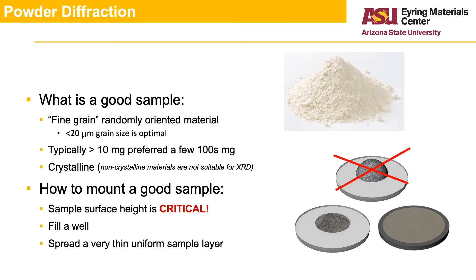First, we make a good sample. The best samples for powder diffraction have the consistency of talc powder, with a fine grain size and grain shapes limiting preferred orientation. The sample quantity should be in the hundreds of milligrams if possible, but when needed, very small amounts such as 10 to 20 milligrams can still provide excellent data.